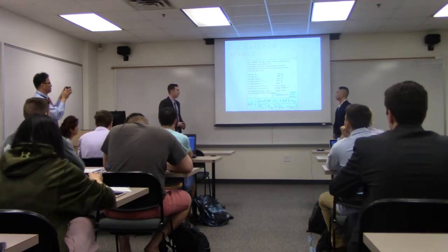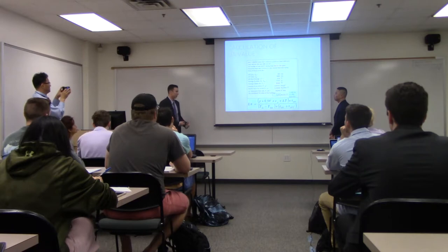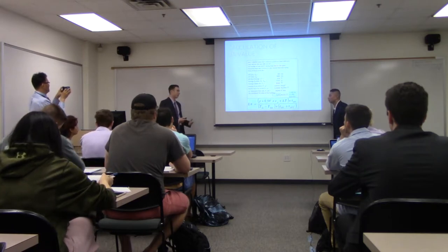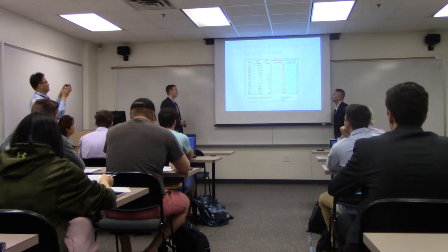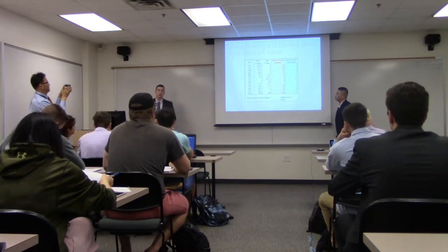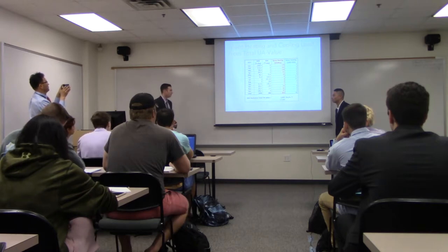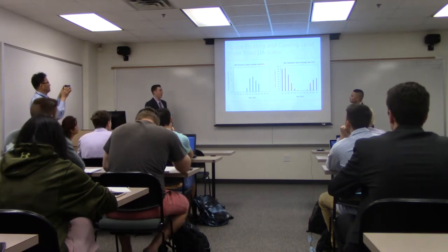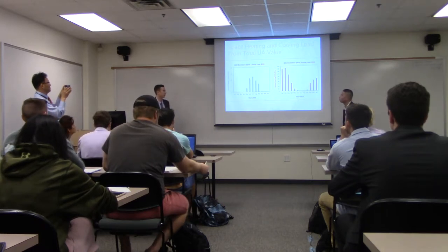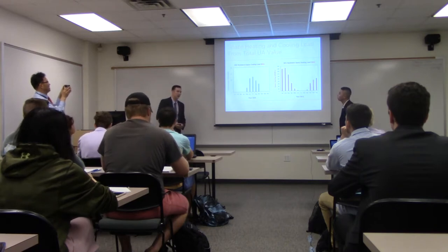Next we wanted to calculate the space heating and cooling loads from the total UA value. We gathered weather data for the heating degree days and cooling degree days, which is basically the average amount of degrees above or below a base temperature of 65 degrees — that's just an agreed-upon base for human comfort. In the summer months it was above that base temperature so the building needed to be cooled, and for the rest of the year it was typically below that so it needed to be heated. All this data was from 2015, the most recent year available, which you can get from multiple weather websites depending on your area.